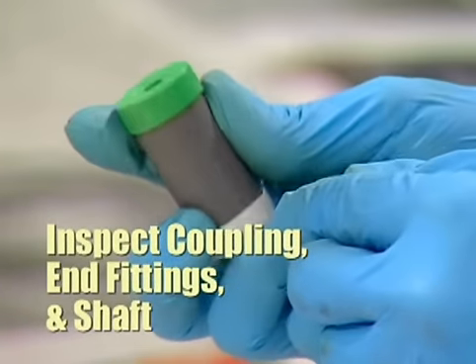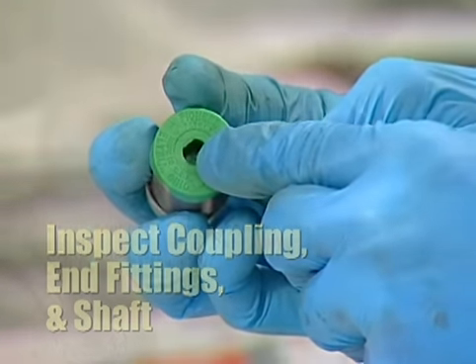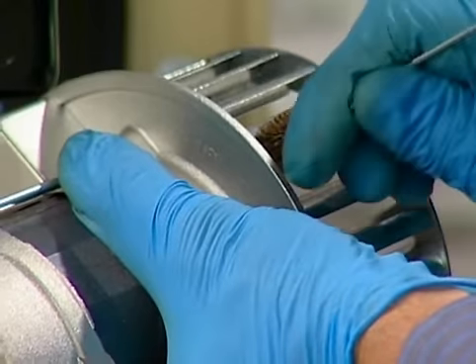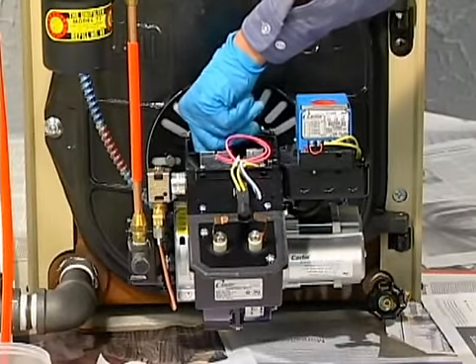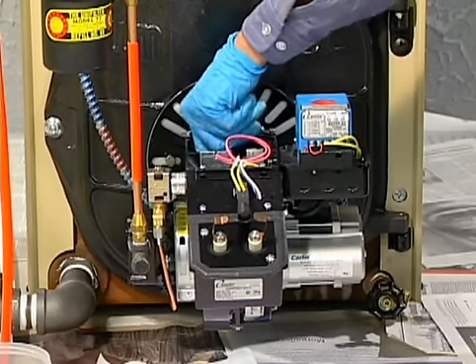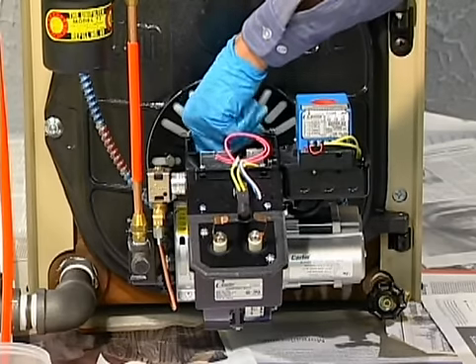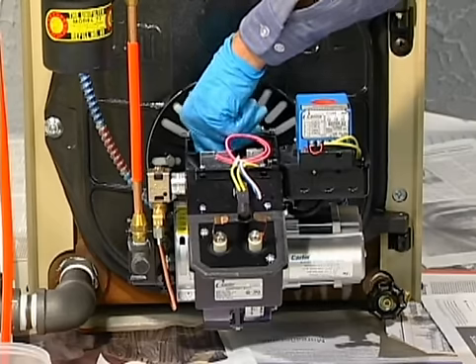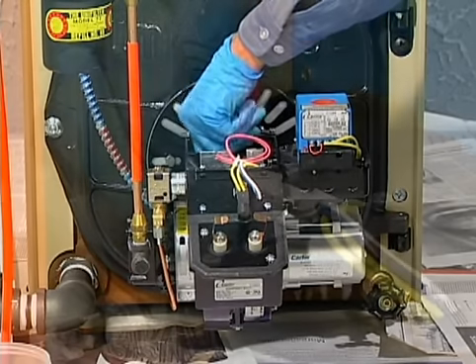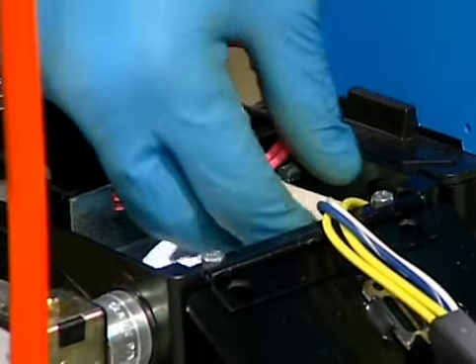Inspect the burner coupling to be sure it isn't worn or stripped. Clean the air inlets and fan using a small brush. After you reinstall the motor, spin the fan a few times to make sure that the motor, fan, and pump are moving freely and that everything is properly connected. Check all wires and connections at the burner.